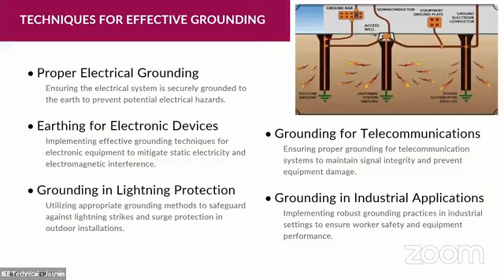Common installation mistakes, technically when it comes to grounding, are improper placement of the grounding electrode. We see in practice that when the grounding electrode hits a rock, it just gets cut off. That means your grounding system is quite compromised - compromised in the sense that its effectivity is reduced, because we are supposed to provide an effective connection to earth or ground with a low impedance path, maintaining lower than 25 ohms or lower than 5 ohms.